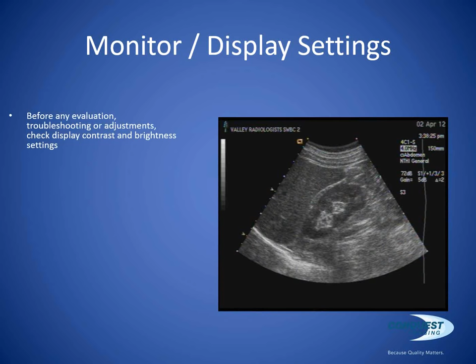First thing you want to do is adjust the room lighting to typical scanning room intensity. Ultrasound rooms are typically very dark, and so you want to adjust the room lighting to simulate the room lighting when a scan is being performed. And then you want to use that grayscale bar to adjust the brightness. Typically grayscale bars are either stepped or graduated, but look for the very bottom of the bar. You want to bring the background brightness up to the point where it's a very light gray where you can see the entire bar, and then you start bringing it down again where the bottom of the bar is just barely visible. At that point you have the brightness or the background set properly.